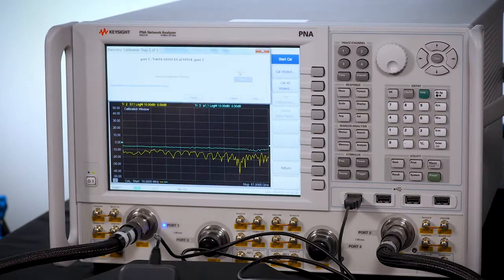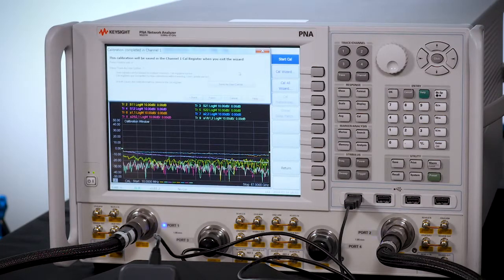Now the E-Cal is going to simulate short, open, load, and through connections just like it would with a mechanical cal, and it's done. This calibration is accurate, repeatable, and fast. There's plenty of electronic calibration modules to choose from these days, so what should you consider when shopping for one?